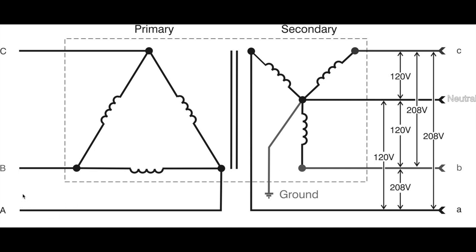So on the primary side you come in with your three phases and they are wired up in this delta configuration. And then there is the magnetic core in the middle. And then on the right side you have this Y configuration, and that means you have in the middle the possibility to get out the neutral. And that's exactly what I needed. I needed the four-wire output for the three phases, and the fourth is the neutral wire. So when you measure the voltage between the phases directly, then you will measure 400 volts. But if you measure between a phase and a neutral then you will get 230 volts.